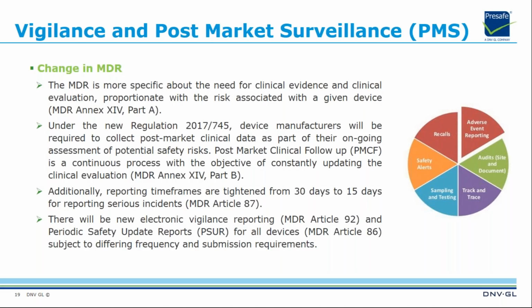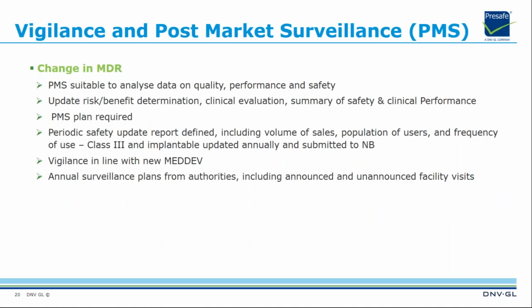timeframes are tightened from 30 days to 15 days for reporting serious incidents. So it's decreased from 30 days to 15 days in the new regulation, Article 87. There will be new electronic vigilance reporting and periodic safety update reports for all devices, subject to differing frequency and submission requirements. Also, PMS is suitable for analysis of data on quality, performance, and safety. Update of risk-benefit determination, clinical evaluation, summary of safety and clinical performance, and PMCF plan is required.